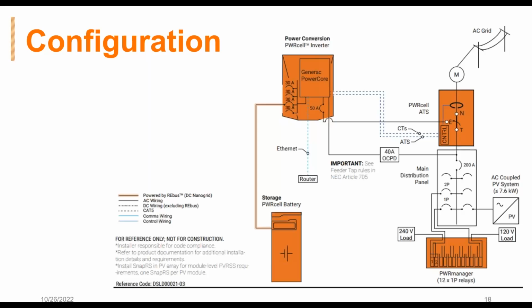So if you have a load on a 60 amp breaker, you could pull that through the power manager. Anything on a 60 amp breaker is going to be a 2-pole load, so you're going to pull both wires into the power manager and then back into the breaker. Each circuit in the power manager is rated for 60 amps. But the power manager itself has nothing to do with how much power the actual inverter and battery cabinet can push.